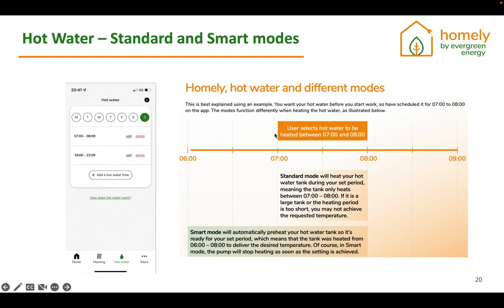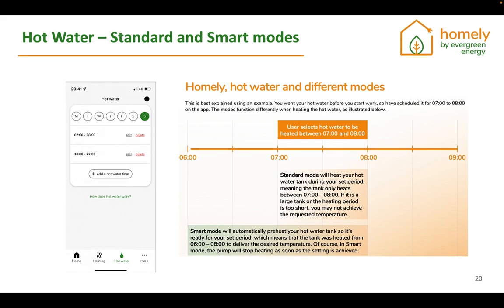So on the heat pump, it will actually turn on the reheat of the hot water, and that will run between 7 and 8 o'clock in the morning. In smart mode, what we do is we add another hour before the time that you are going to get up, so that by the time the customer gets up at 7 o'clock, the hot water would have been in reheat for that whole hour, and the customer would then have hot water already. So this is kind of like a preheat function in the smart mode.